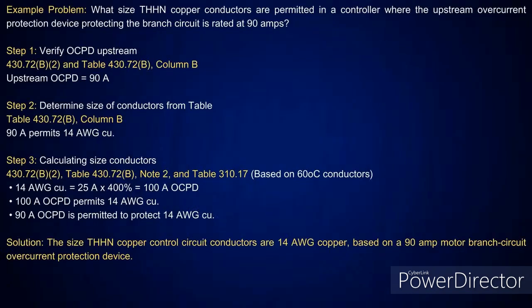And then this one, what this is going to get into, we're basically proving something here more than anything. And this is over in 430.72B2. Like this first one we're going to talk about, this is where they're sizing some THHN copper conductors that are permitted in a controller where the upstream overcurrent device protecting the branch circuit is rated 90 amps. So when you look at table 430.72B, column B, it's going to tell you 90 amps permits number 14. But how do I prove that?